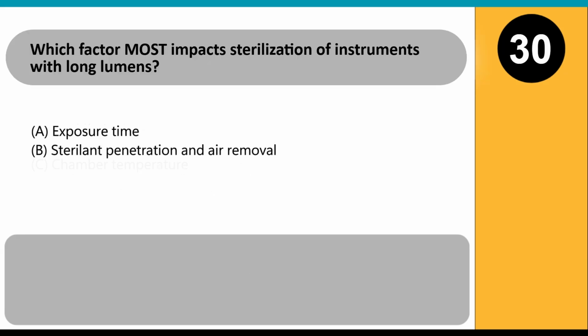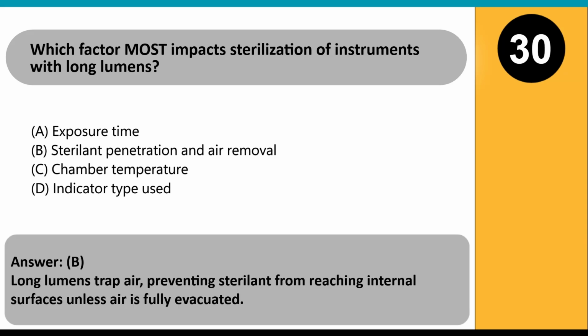Which factor most impacts sterilization of instruments with long lumens? A. Exposure time. B. Sterilant penetration and air removal. C. Chamber temperature. D. Indicator type used. Answer B. Long lumens trap air, preventing sterilant from reaching internal surfaces unless air is fully evacuated.